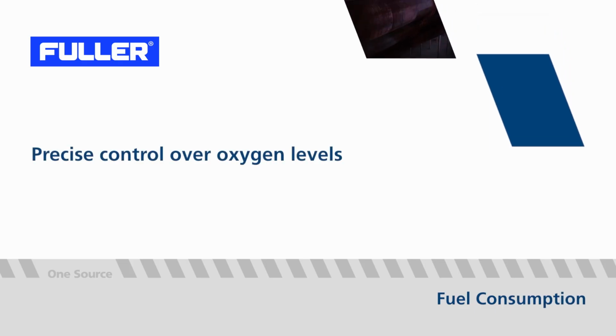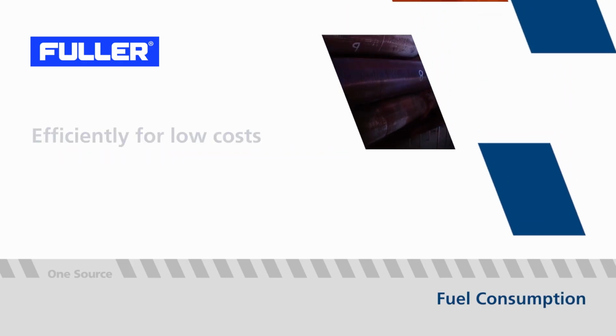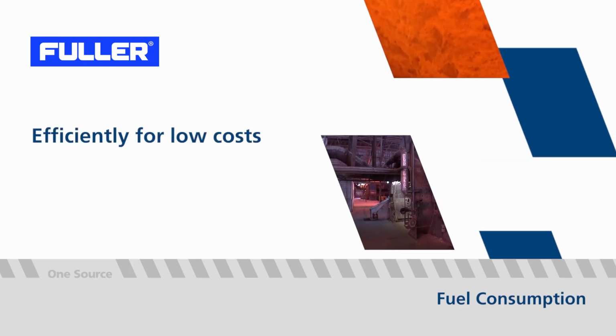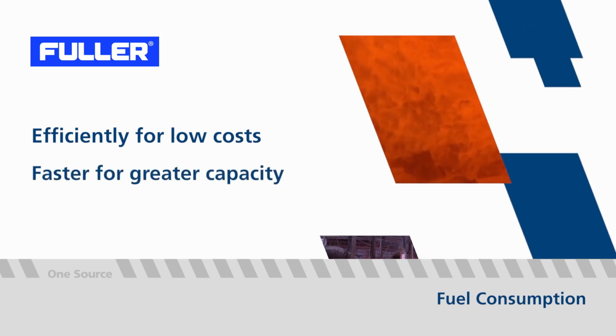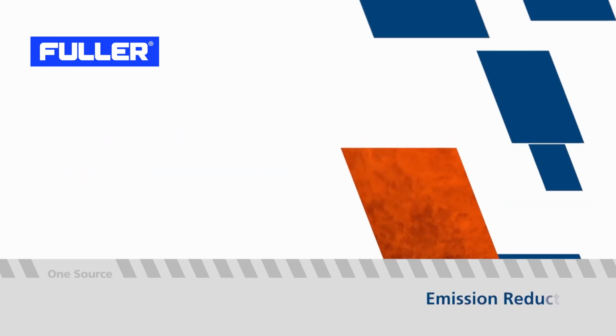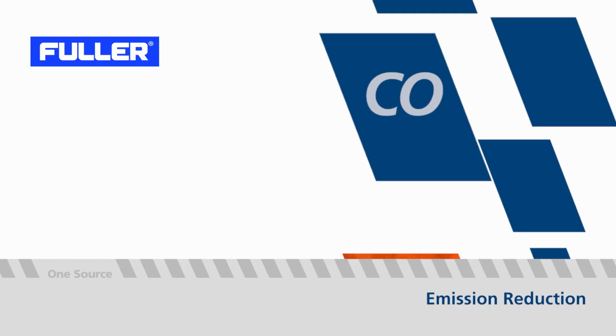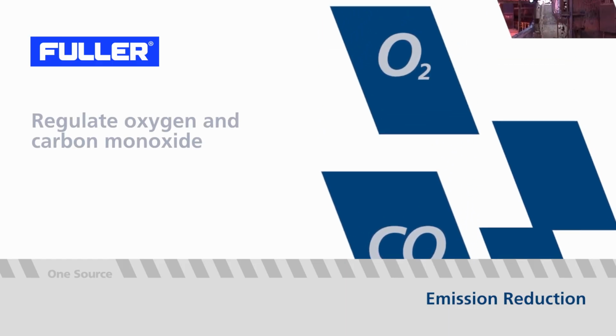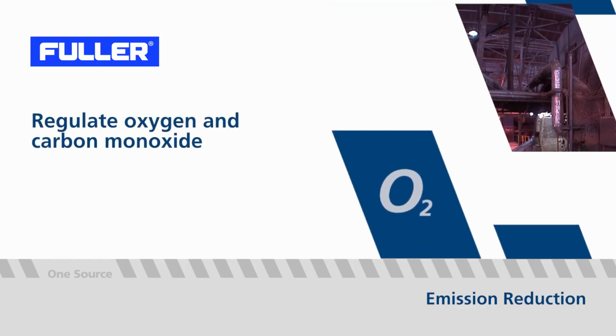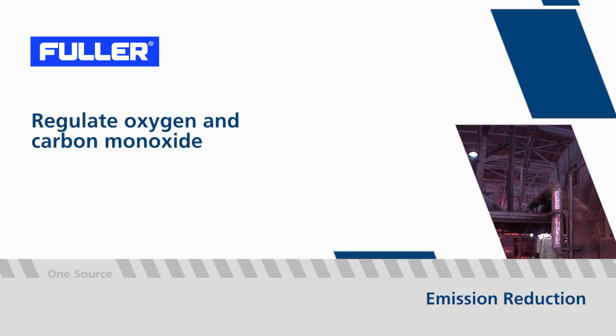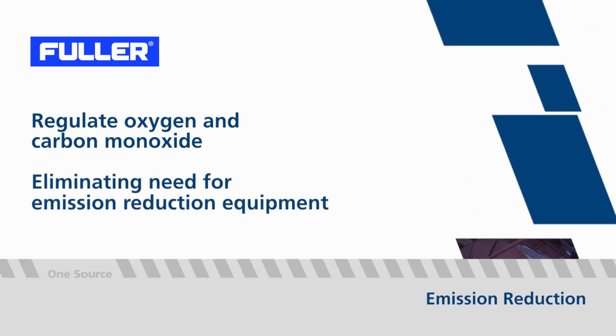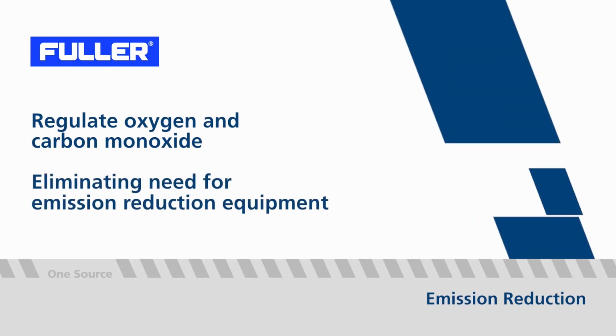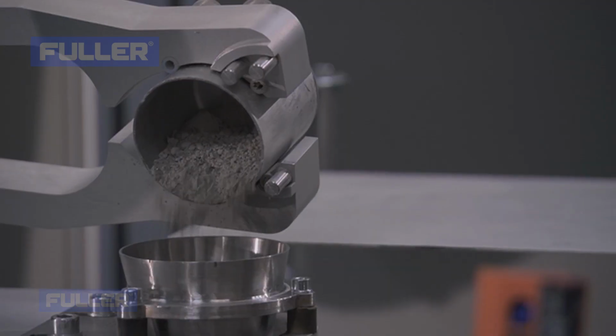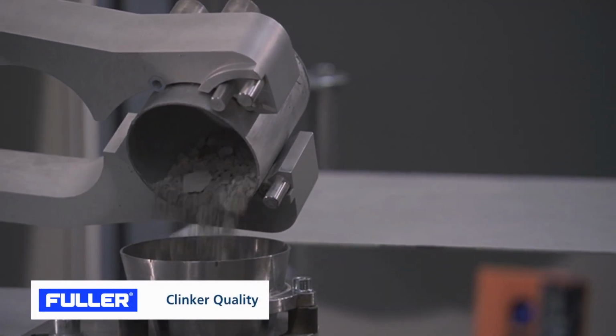It also gives operators precise control over oxygen levels so that fuel can be burned slowly and efficiently for lower production costs, or faster for a higher throughput and greater capacity. Based on gas analysis data, operators are able to regulate the oxygen and carbon monoxide produced in the kiln, optimising combustion and avoiding the need for expensive emission reduction equipment to remove pollutants at a later stage.